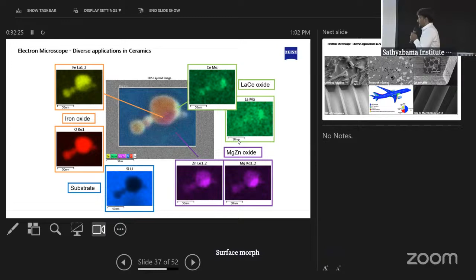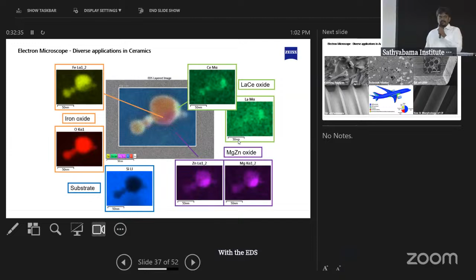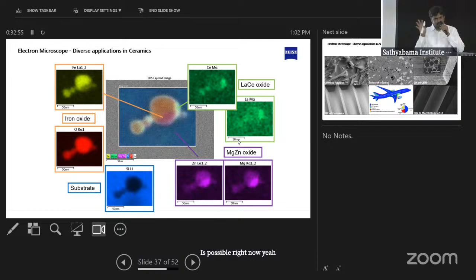So it was always challenging, but with the recent improvement in the EDS detector, not necessarily only imaging, this data was captured at just 2 kV of acceleration voltage. You can see here the length scales are like 50 nanometers, and the particles you're able to see are on the order of 10 to 20 nanometers. So chemical composition analysis, even on a non-conducting sample, is possible right now, which was not possible a decade back, right? All right.